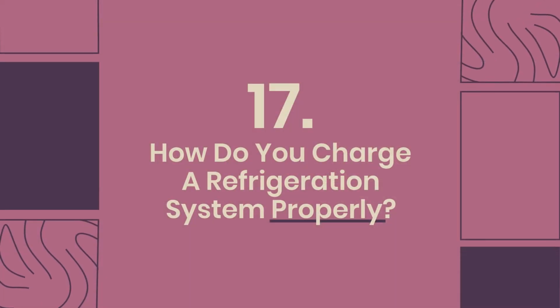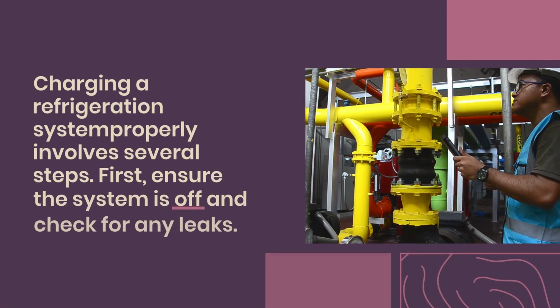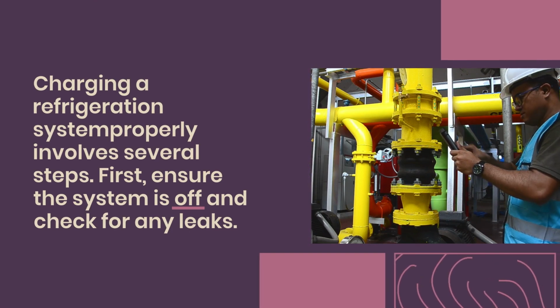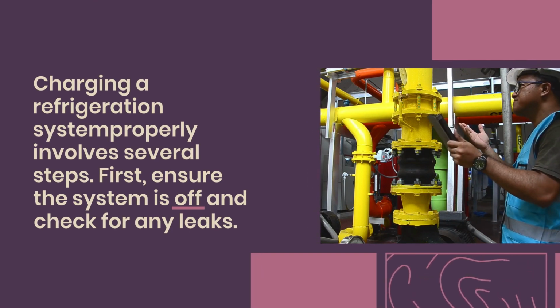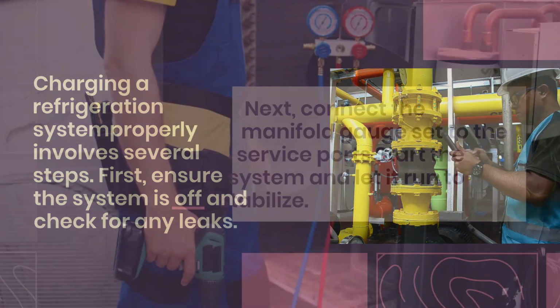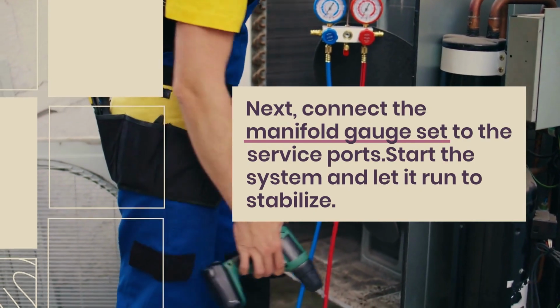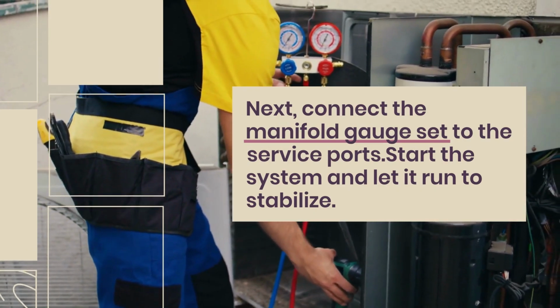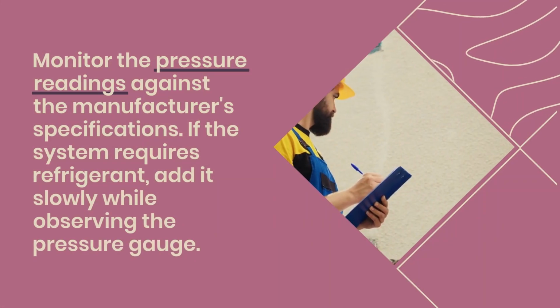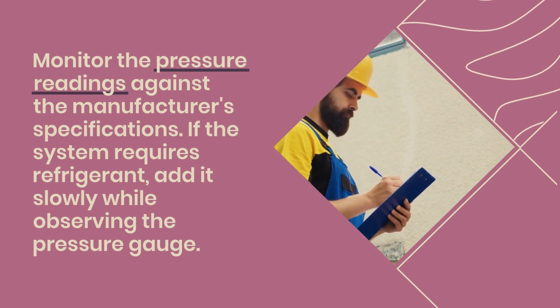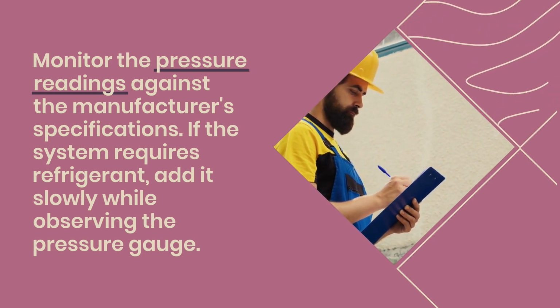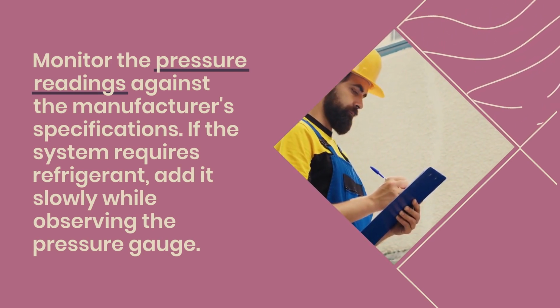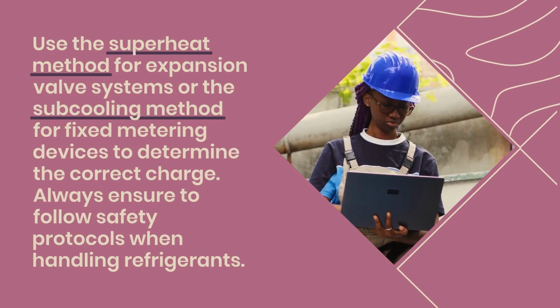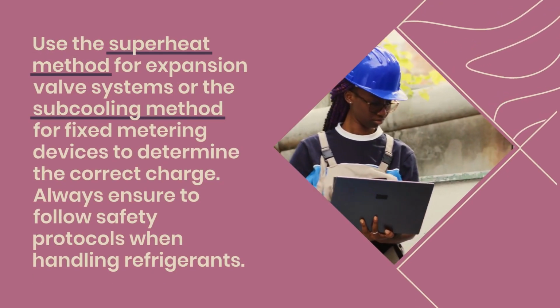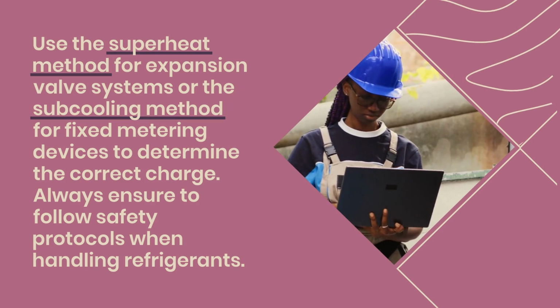17. How do you charge a refrigeration system properly? Charging a refrigeration system properly involves several steps. First, ensure the system is off and check for any leaks. Next, connect the manifold gauge set to the service ports. Start the system and let it run to stabilize. Monitor the pressure readings against the manufacturer's specifications. If the system requires refrigerant, add it slowly while observing the pressure gauge. Use the superheat method for expansion valve systems or the subcooling method for fixed metering devices to determine the correct charge.